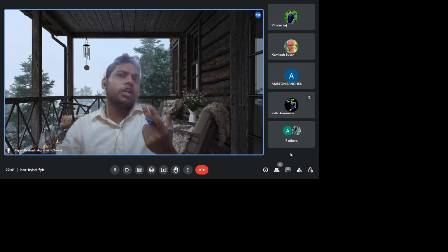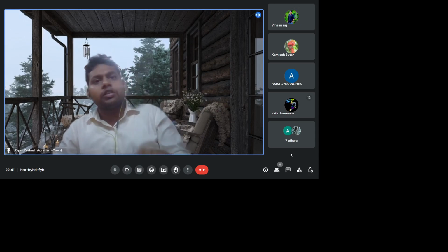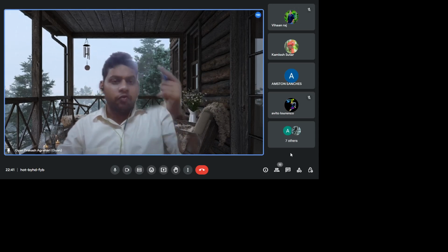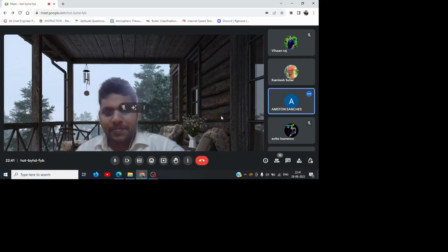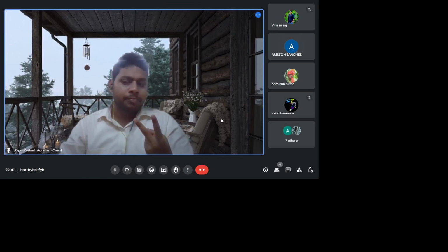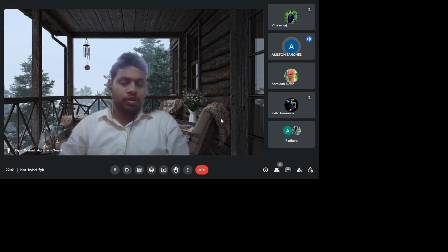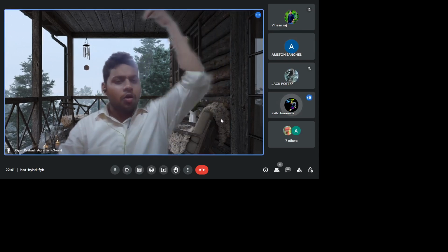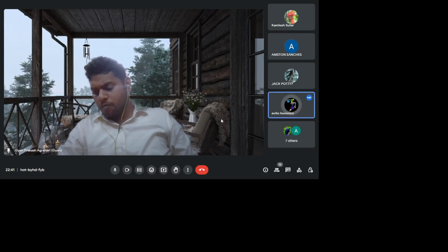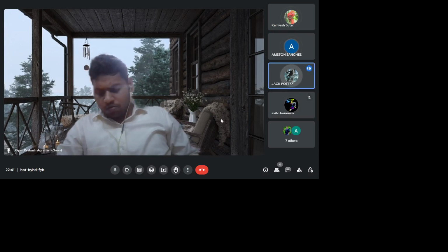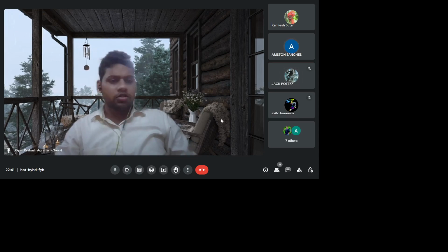It is not of two types, it is two in number, for safety reasons: if one is not showing correct, the other will. For the same reason, we have two safety valves. Apart from that, you also have a separate steam pressure gauge. In the water gauge glass, we are only looking at the water level, we don't care about the steam pressure. That's why the steam pressure gauge is there.